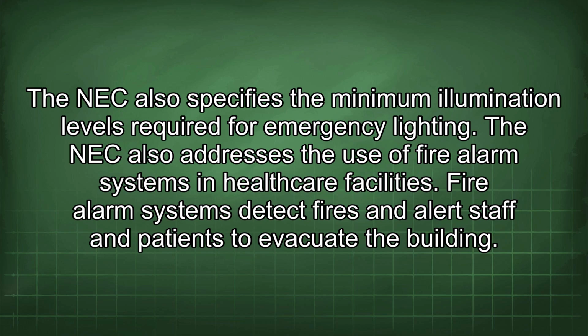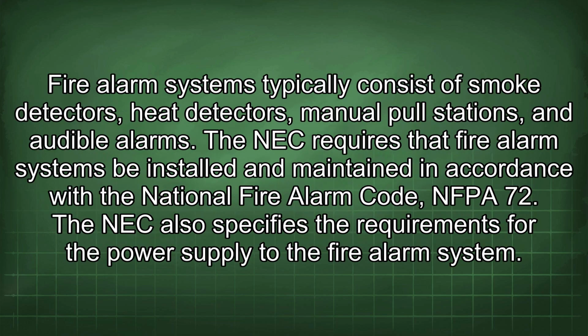The NEC also addresses the use of fire alarm systems in healthcare facilities. Fire alarm systems detect fires and alert staff and patients to evacuate the building. Fire alarm systems typically consist of smoke detectors, heat detectors, manual pull stations, and audible alarms. The NEC requires that fire alarm systems be installed and maintained in accordance with the National Fire Alarm Code, NFPA 72. The NEC also specifies the requirements for the power supply to the fire alarm system.